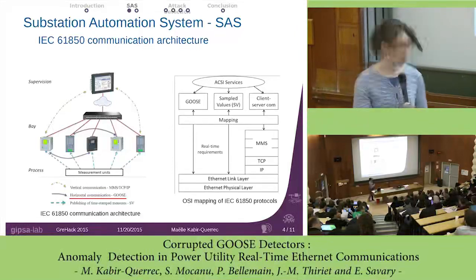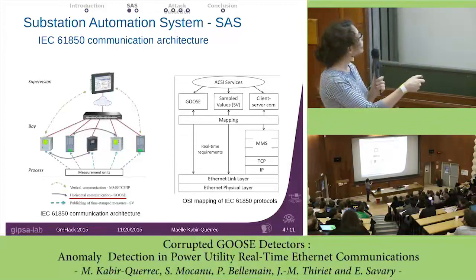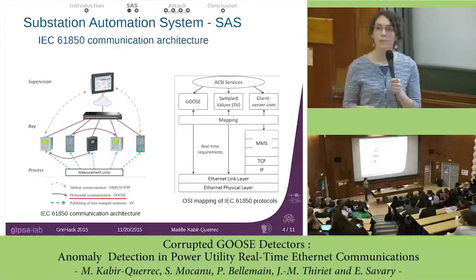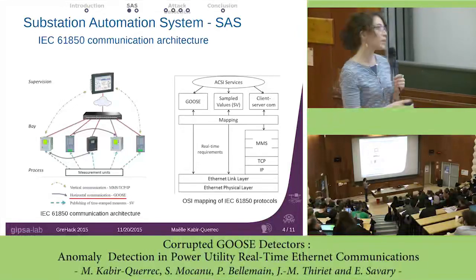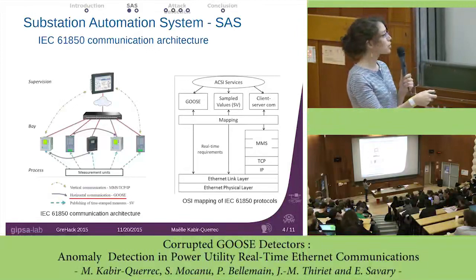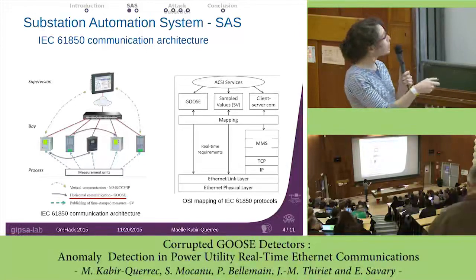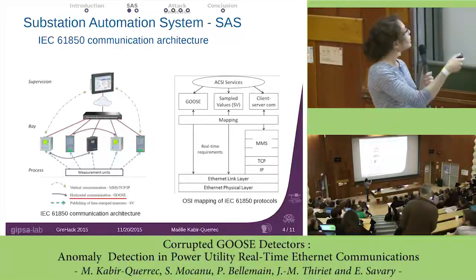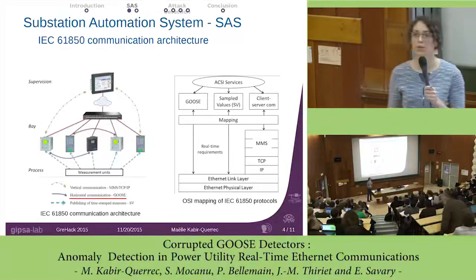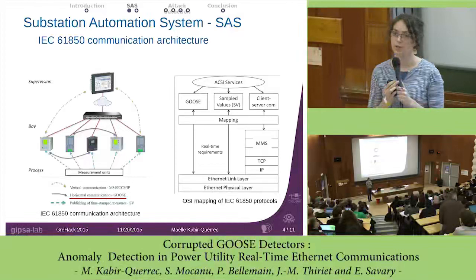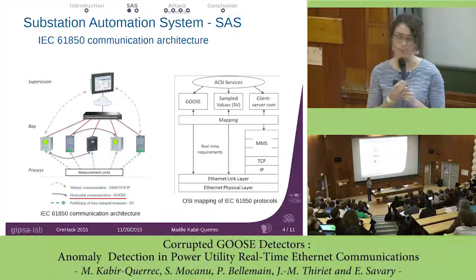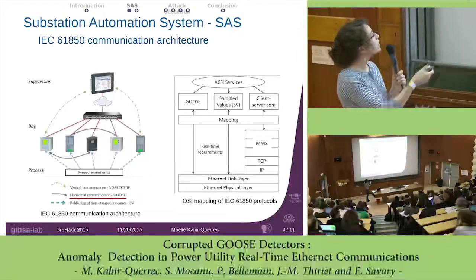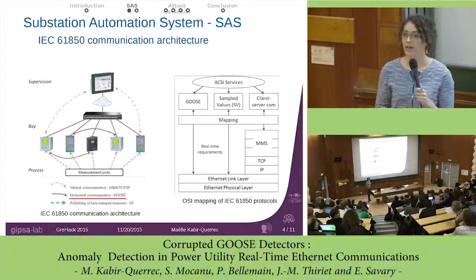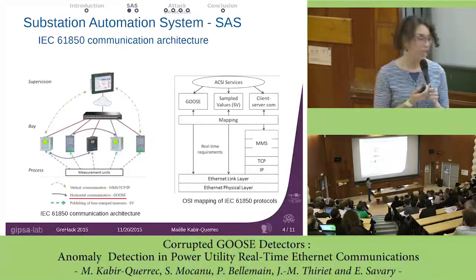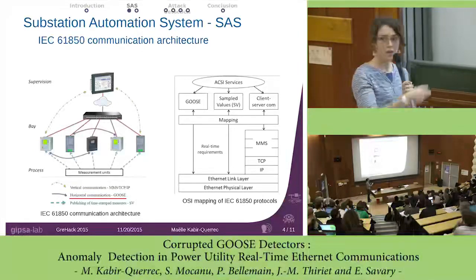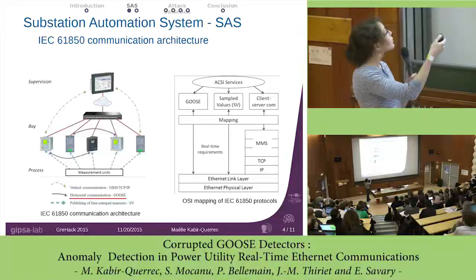You have 3 levels. The base one is the process level, where you have circuit breakers and other machines, and you have measurement units on those machines. The second level is the bay level, that is the actuators. We call those devices intelligent electronic devices. Actually, they are ICS, industrial control systems, dedicated to substation automation. And the third level is supervision. I also call it SCADA. The previous speaker, Mr. Ben Aloui, said SCADA was all of it, but if I use the term SCADA, I will refer to the supervision level.